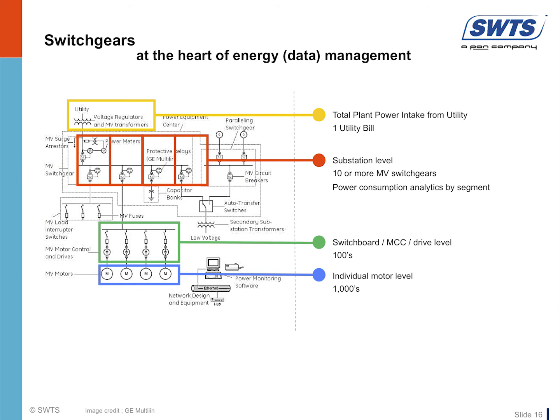Starting your digital data collection at the MV switchgear level is a clever first step, for two related reasons. The first has to do with choosing to collect energy consumption data—I will get to that later. The second is because it strikes a reasonable balance between too little and too much data.